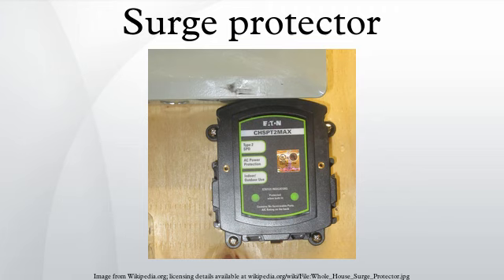Underwriters Laboratories, a global independent safety science company, defines how a protector may be used safely. UL 1449, 3rd edition became compliance mandatory in September 2009 to increase safety compared to products conforming to 2nd edition. A measured limiting voltage test, using 6 times higher current, defines a voltage protection rating. For a specific protector, this voltage may be higher compared to a suppressed voltage ratings in previous editions that measured let-through voltage with less current. Due to non-linear characteristics of protectors, let-through voltages defined by 2nd edition and 3rd edition testing are not comparable. A protector may be larger to obtain the same let-through voltage during 3rd edition testing. Therefore, a 3rd edition protector should provide superior safety with increased life expectancy.